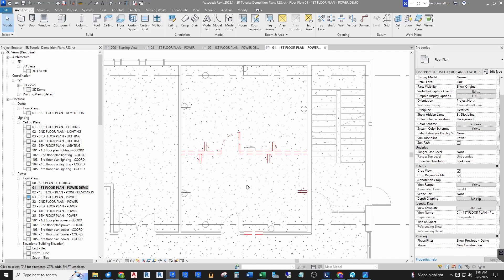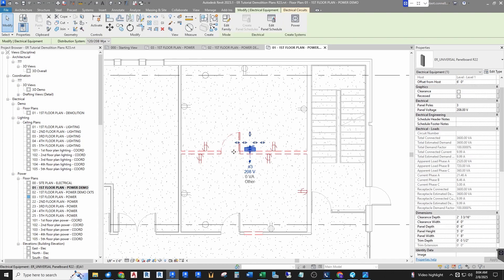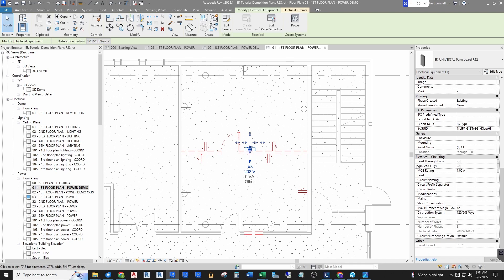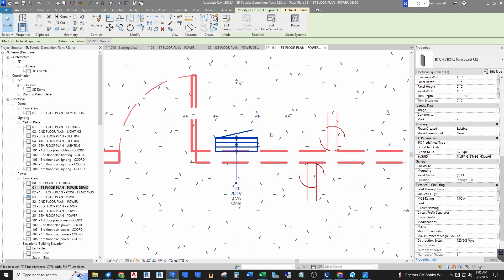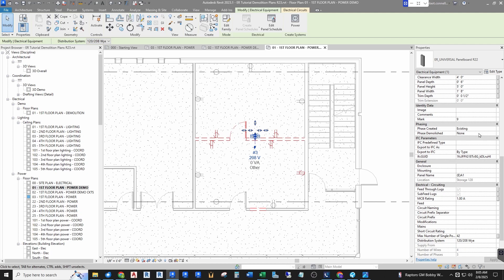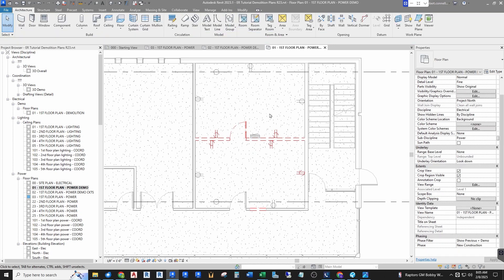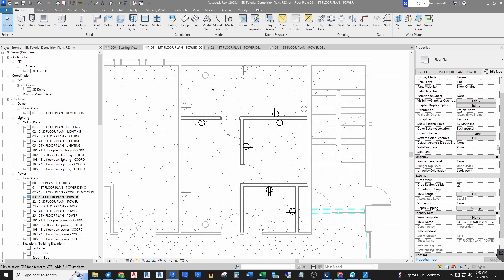Yes, if I click on for example this existing panel board I can get to phasing information over on the right. Here under phasing I can say it was created in existing and it makes it kind of a lighter line type, not so bold. I could say phase demolished new construction. If I'm just getting rid of this panel and I don't care about what circuits are attached to it or anything like that I'm fine. But in this case as you can see I have some receptacles that will remain—these light colored ones that are not red, not dashed—they will remain. This is what my new power plan is going to look like, some existing and some new. I want to power these up to a panel in a new location, so I'll remove them from the existing panel, put them in the new panel which I haven't shown yet.